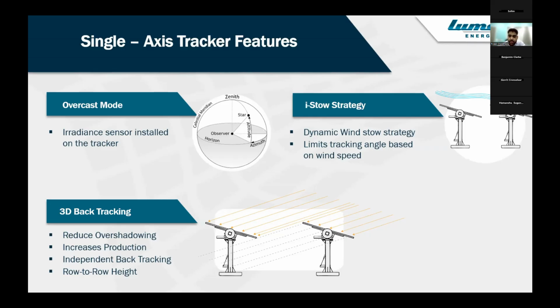With the iStow strategy, this is more of a dynamic wind stow strategy. Instead of setting it at a safe angle, it limits the tracking angle based on wind speed. For example, at 18 meters per second instead of tracking 60 to 60 degrees, the wind speed may increase to 20 meters per second, and then you start tracking at 50 to 50.